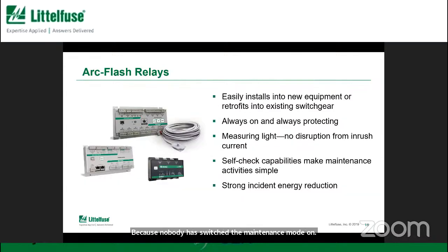So we really feel that arc flash relays are an excellent way to provide arc energy reduction. We'll talk more about that here. A few of the reasons: it's always on. Once these relays are installed and working, they're always watching for the arc. They don't rely on somebody to turn them on or remember to turn them off. They're just always there in the background. So it takes away that element of human error that can get in the way. The system is also quite easy to install, both for new equipment and for retrofit. If you have existing cabinets, these arc flash relays are quite easy to put into an existing system, which is also quite important.